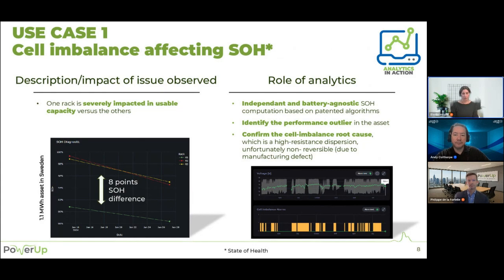Let's go back to why it's important that a battery has all its cells balanced. If that's not the case, it will not be fully operational. You'll have impacts such as loss of capacity, which reduces usage of the battery and the money you can earn with it. You might also see early aging of the battery, requiring more maintenance and more maintenance costs. And of course, this can lead to safety risks, as excess charge or discharge of a cell could lead to overheating.